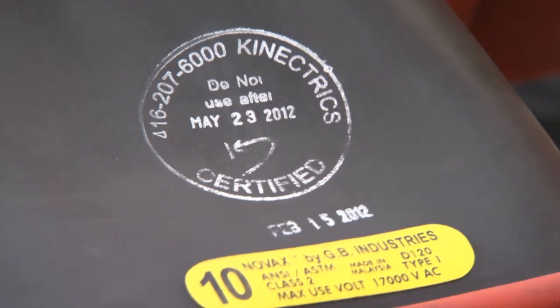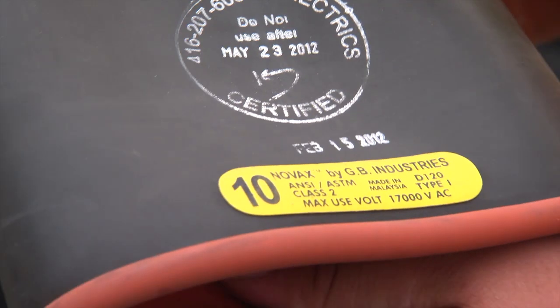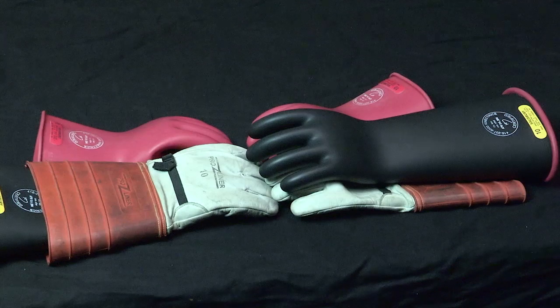Check the manufacturer's stamp that appears on the cuff of each glove for the class and maximum voltage rating. The glove should be Class 2, which means it has an industry rating of 17,000 volts phase to phase. However, the Hydro One rating for Class 2 gloves is 15,000 volts phase to phase. Most rubber gloves are similar in construction, so the manufacturer's stamp is the only way to confirm the class. Check the testing lab stamp for the Do Not Use After date. Rubber gloves must be retested at a certified lab at least every 90 days and are never to be used beyond their expiry date. Perform a visual test and an air test.